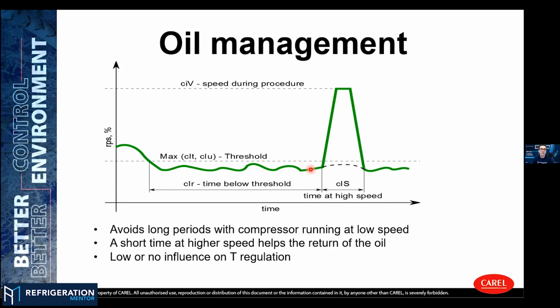Changing the temperature for a few minutes, so all these parameters, like you said, will automatically be programmed through Modbus when you put in a new compressor, so you don't have to change these parameters. Is that correct? Yeah, it comes already embedded in the software. For example, some OEMs manufacturing these units have done a lot of lab tests and came to a very precise and correct list of parameters that can be changed. What we do in general is have some parameter values that are good for 90% of the cases, not 100%, but most cases we can cover with the standard parameters.